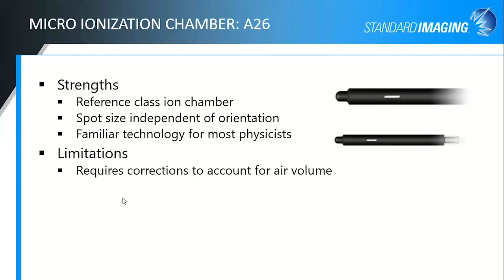So strengths of the A26 is it is a reference class ionization chamber. It was designed to be that way right from the start, based on the findings from Jessica Miller's thesis. The spot size is uniform, independent of orientation. And another strength really is that ion chambers are familiar technology for most physicists. It's something we've used for our entire careers, and we're quite comfortable with that.